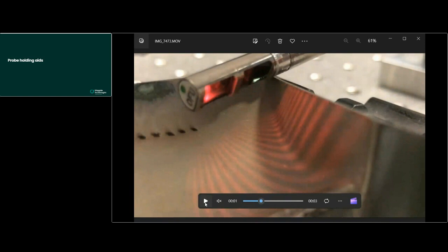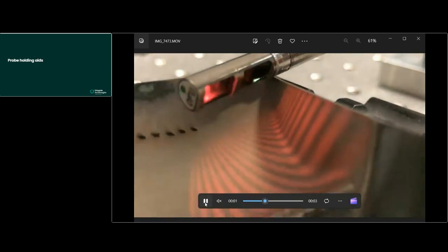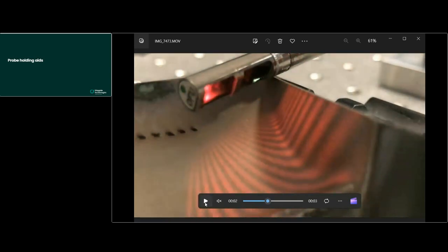points upon which the LED array firing off the fringe pattern from the LEDs from, in this case, the 3D phase measurement side-facing tip, the green tip, is projecting onto the surface, and as I pause it again through the clip, it's acquiring the signal back onto the detector in a matter of milliseconds.